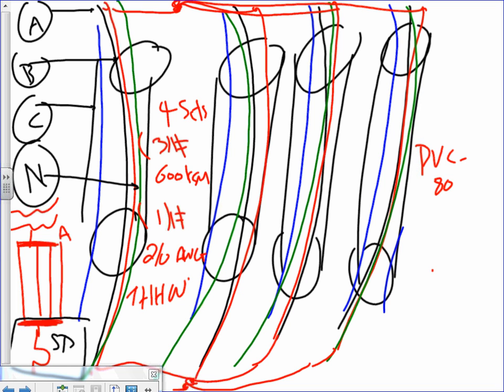You run outside, don't you need metal? We're underground. Okay, here's the rule of thumb. If you don't know how to wire, if you go underground, your conduit of choice... Now remember, you can do anything you want based on the code, but your conduit of choice when you go underground is what? PVC. Why? Anybody know? Rust is the keyword. Underground. Am I clear about the word underground? This is your conduit of choice. Now, can I use rigid underground? Yes. Rigid steel will rust. Not a good choice. That's why you go with PVC.